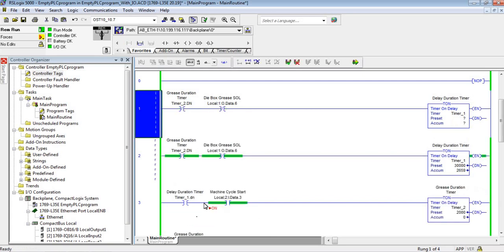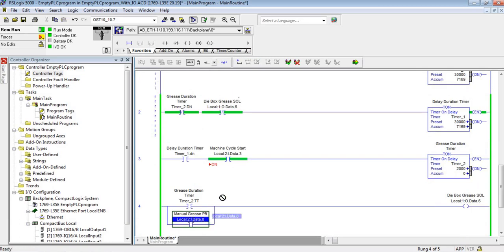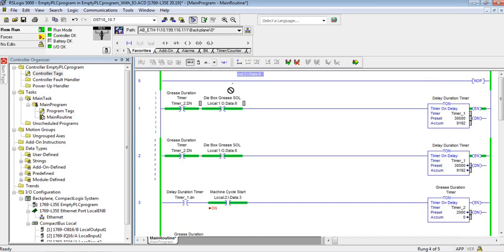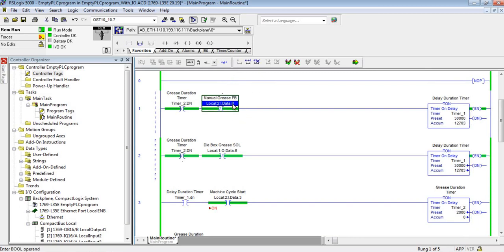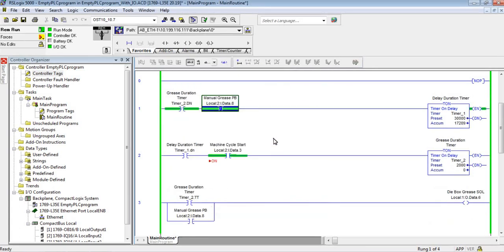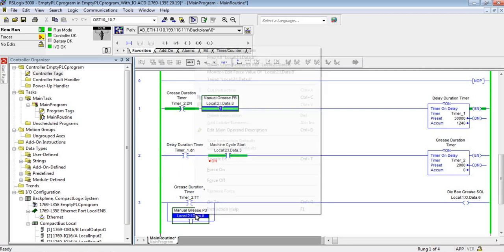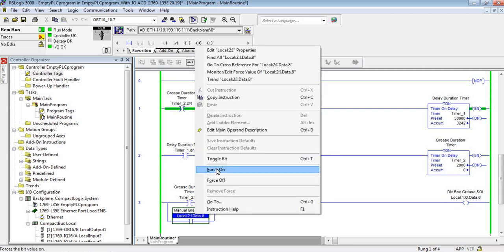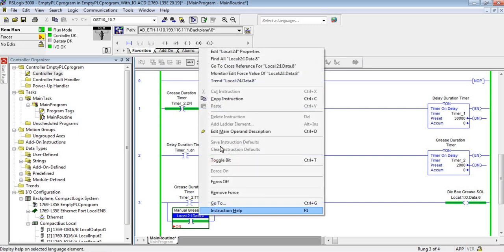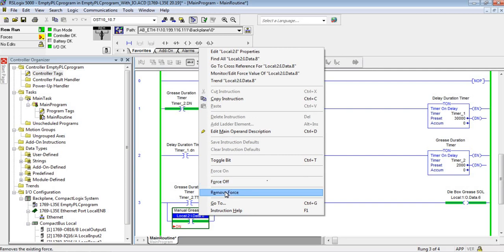You could potentially put this normally closed to the push button, but in real life you have to run a wire all the way out to the push button, wherever that is. That could be a long ways away. It's not undoable, but it's much easier to do this in the logic. Just force it on, boom, everything's off. You got your grease and your timers are off. Remove the force and they start up again. It's so nice. Now let me show you what this looks like without a PLC.